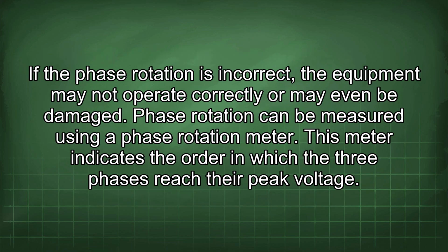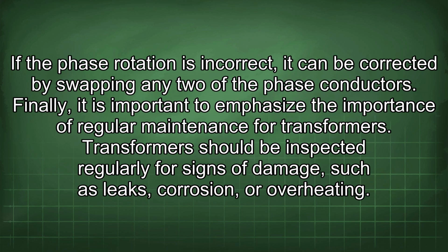If the phase rotation is incorrect, the equipment may not operate correctly or may even be damaged. Phase rotation can be measured using a phase rotation meter. This meter indicates the order in which the three phases reach their peak voltage. If the phase rotation is incorrect, it can be corrected by swapping any two of the phase conductors. Finally, it is important to emphasize the importance of regular maintenance for transformers.